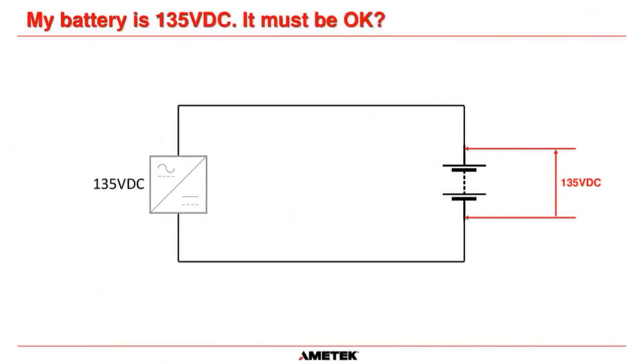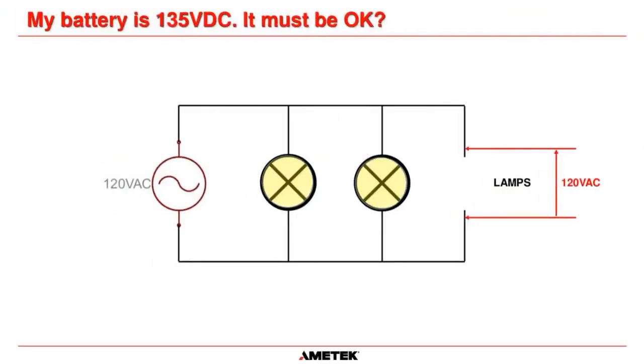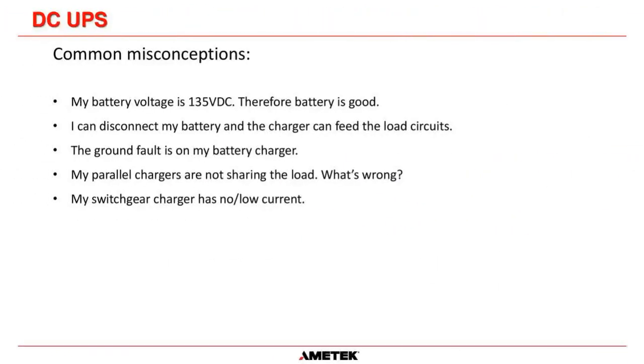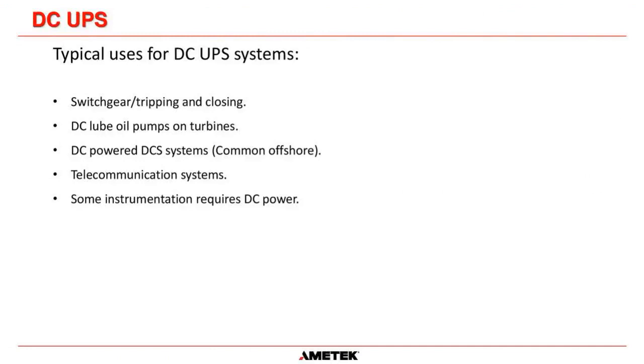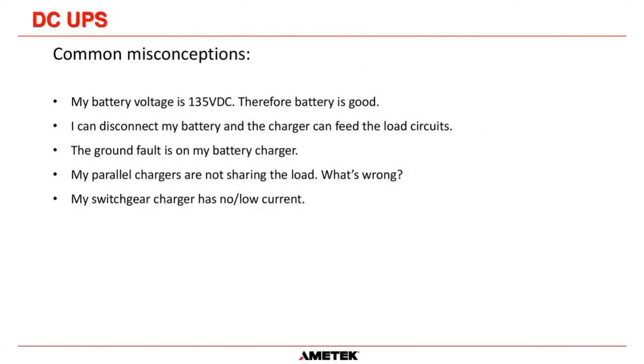While I'm getting there, we have another question. If you have the battery disconnected on a switchgear and you have a fault causing the breaker to trip, can the charger respond quickly enough? No, absolutely no, it can't. And that's one of the reasons why you should never have a battery disconnected from your switchgear system. You should always put a temporary battery in place before you remove the other battery, because any fault or transient load on that system will inevitably pull down the voltage of the charger.